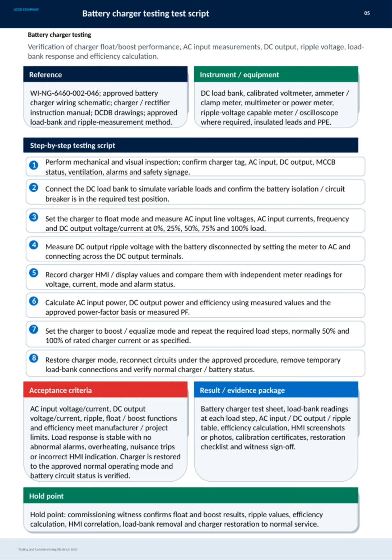Throughout the process, all parameters like AC and DC voltages and currents, ripple levels, and efficiency must meet the manufacturer's and project specifications. We also check that the load response is stable without any abnormal alarms or incorrect indications. Documentation includes comprehensive test sheets, readings for each load step, efficiency calculations, HMI screenshots, calibration certificates, and a restoration checklist.